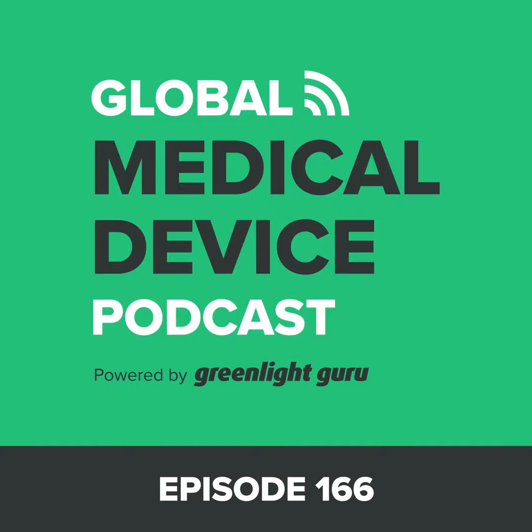Yeah. And I'm going to make a statement that I think is universal, and we can peel it apart if necessary. But folks, every single medical device needs to address biocompatibility. Now, I know some of you may be saying, but my device is software. It's not patient contact. Okay, valid. You still need to address it from the eyes of the regulatory perspective and from your own perspective. If it's not applicable, then you need to explain why it is not applicable. But this is not a topic that you can ignore. I mean, it's table stakes, in my opinion, for every single medical device. You have to address biocompatibility.